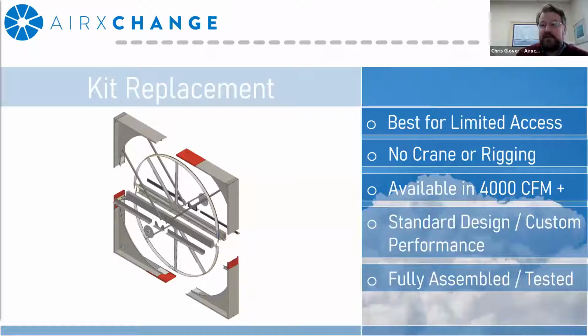Typical diameters range from 58 inches to 165 inches, which equates to 4,000 to 65,000 CFM. So they get to be quite big. The structure of these units all use standard fabricated parts, which cuts down on the cost and lead time. But even though you're using standard fabricated parts, the performance of these devices can be tailored to any application. And in most cases I've come across, you can even provide better performance in terms of thermal and latent transfer and pressure drop than what was existing. These components are assembled in the factory, and then they're broken down for shipment to the site.